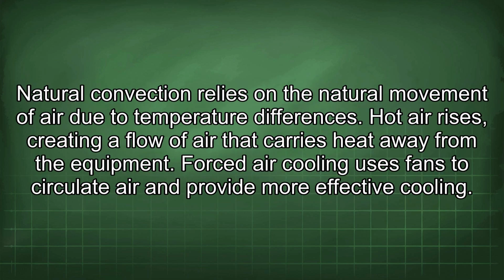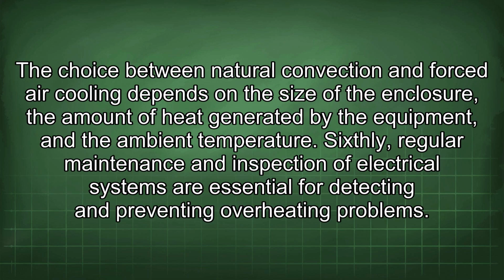Natural convection relies on the natural movement of air due to temperature differences. Hot air rises, creating a flow of air that carries heat away from the equipment. Forced air cooling uses fans to circulate air and provide more effective cooling. The choice between natural convection and forced air cooling depends on the size of the enclosure, the amount of heat generated by the equipment, and the ambient temperature.